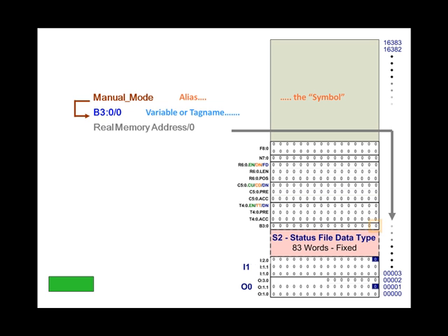When you are creating logic, you can type in the symbol, and it will bring the base variable with it. With this programming software, the symbol is limited to a single line of 20 characters. If more descriptive nomenclature is needed, this programming software allows you to add a description and associate it with a variable. Although I show only 3 lines, the descriptions are limited to 5 lines of 20 characters, almost enough to write a book. The programming software will not inhibit you from assigning the same description to 2 separate variables, so beware. It's not like the symbol, where it will prevent you from using the same symbol twice. It will allow you to put anything you want in those 5x20 characters for the description.